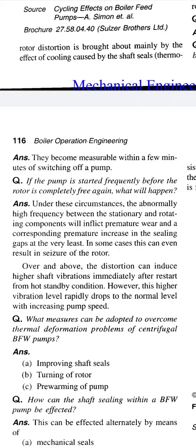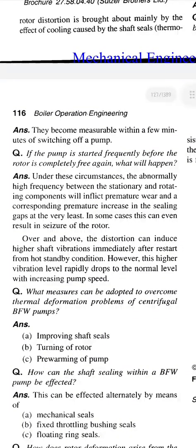Question: if the pump is started frequently before the rotor is completely free again, what will happen? Answer: under these circumstances, the abnormally high friction between the stationary and rotating components will inflict premature wear and a corresponding premature increase in the sealing gaps at the very least.